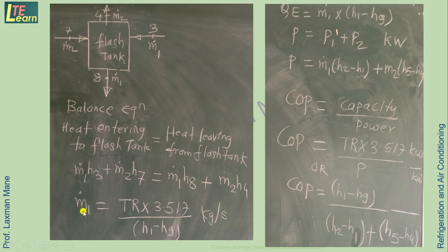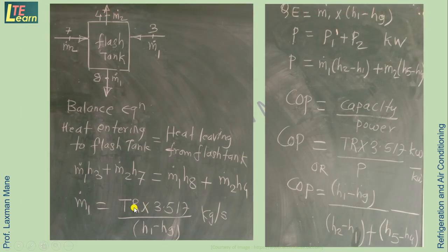Mass flow rate m1-dot can be found from the evaporator capacity: m1-dot equals the evaporator capacity (in TR converted to kW using the multiplier) divided by the enthalpy difference across the evaporator (h1 minus h8). Once m1-dot is known, m2-dot can be obtained from the flash tank energy balance, since all enthalpies are read from the PH diagram.